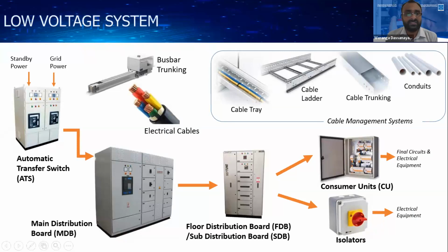When the automatic transfer switch detects that power is available at the standby power supply side, it will feed the main distribution board of the LV system. Then the LV distribution board feeds several floor distribution boards or sub-distribution boards, which are allocated in several zones of the building or premises. Then finally, there are what we call consumer units. I think all of you may know that in your houses there are small distribution boards to distribute the circuits inside your house wiring. That type of distribution board we call a consumer unit. That means the final circuits and the final electrical equipment are all connected to this kind of small consumer unit.